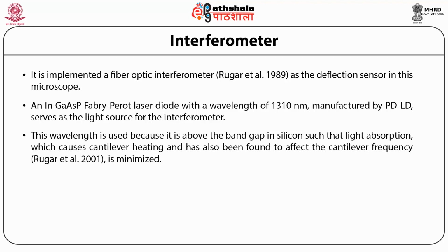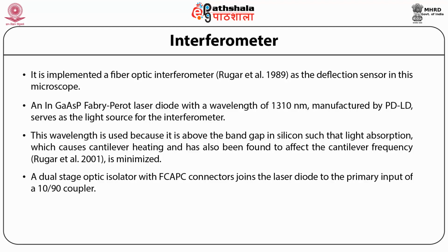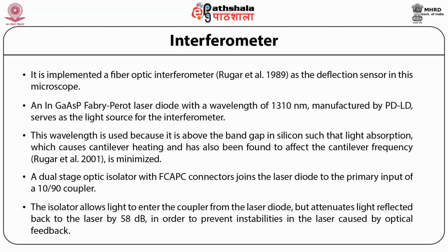This wavelength is used because it is below the band gap energy of silicon, such that light absorption, which causes cantilever heating and has also been found to affect the cantilever frequency, is minimized. The laser diode is packaged with an FC receptacle for simple connection to the optical fiber. A dual-stage optical isolator with an FC-APC connector joins the laser diode to the primary input of a 10/90 coupler. The isolator allows light to enter the coupler from the laser diode but attenuates light reflected back to the laser by 58 dB in order to prevent instabilities in the laser caused by optical feedback.